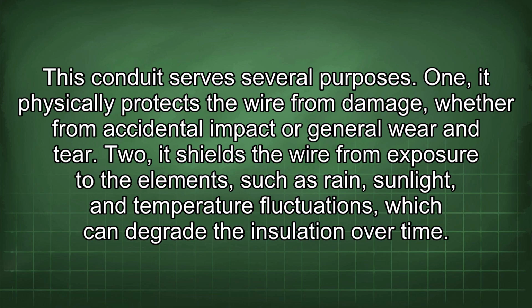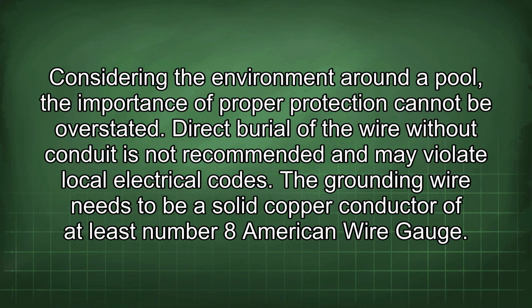1. It physically protects the wire from damage, whether from accidental impact or general wear and tear. 2. It shields the wire from exposure to the elements such as rain, sunlight, and temperature fluctuations, which can degrade the insulation over time. Considering the environment around a pool, the importance of proper protection cannot be overstated. Direct burial of the wire without conduit is not recommended and may violate local electrical codes.